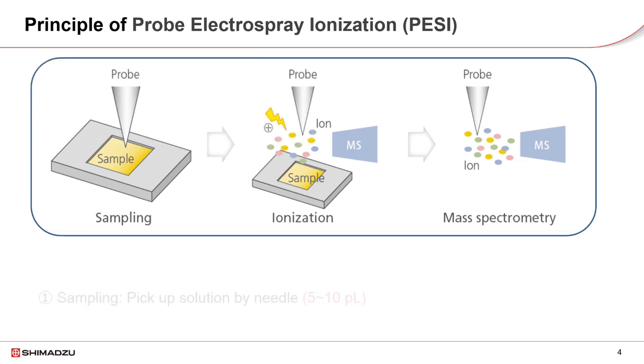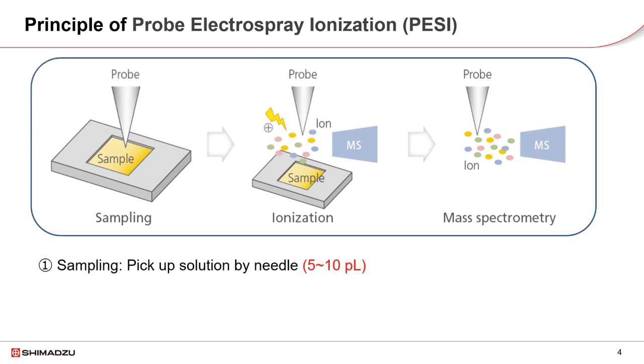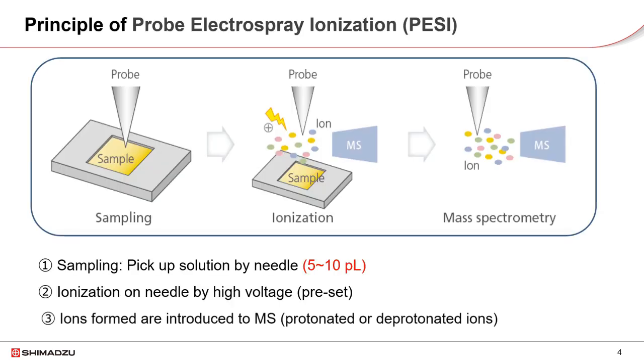This slide further explains how PESI works. Ten microliters of liquid sample is loaded onto a sample plate. The metal needle moves down to pick up 5 to 10 picoliters of the sample each time, and ionization takes place in the high-voltage electrical field. The ions formed are protonated ions in positive mode, or deprotonated ions in negative mode.